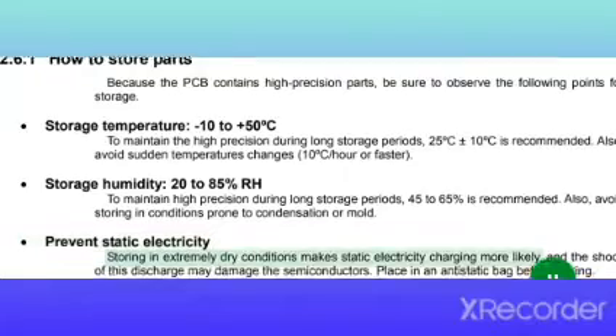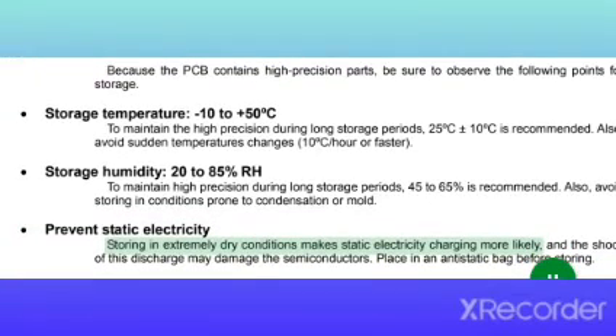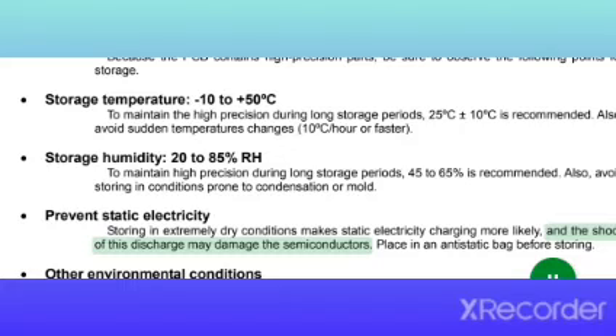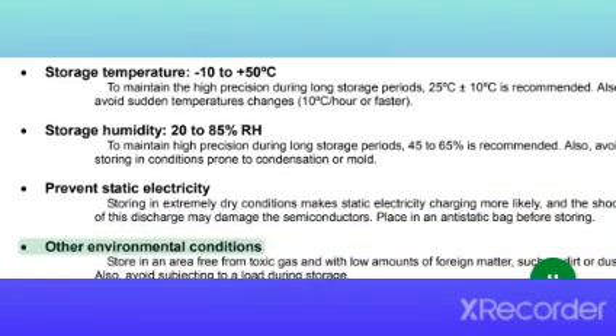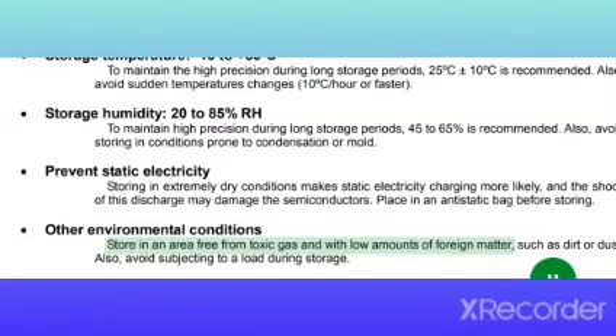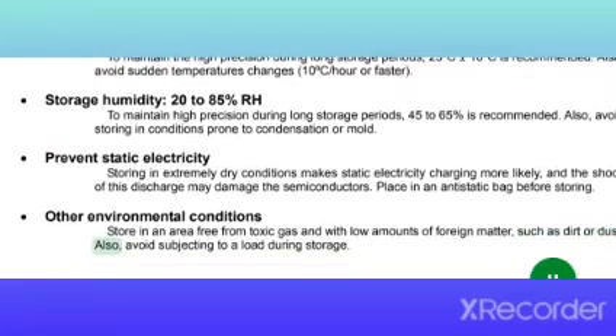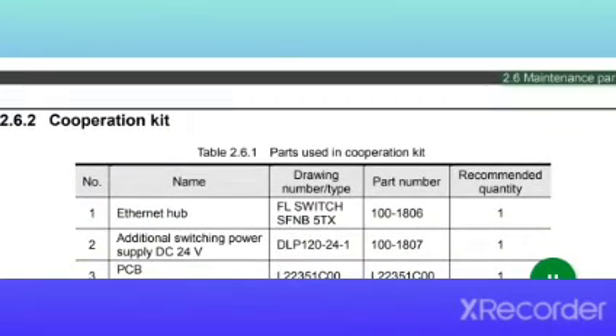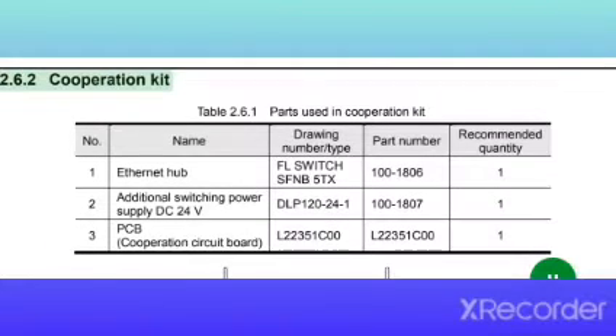Prevent static electricity. Storing in extremely dry conditions makes static electricity charging more likely, and the shock of this discharge may damage the semiconductors. Place in an anti-static bag before storing. Other environmental conditions: store in an area free from toxic gas and with low amounts of foreign matter, such as dirt or dust. Also, avoid subjecting to a load during storage. 2.6 Maintenance parts, 2 to 31.